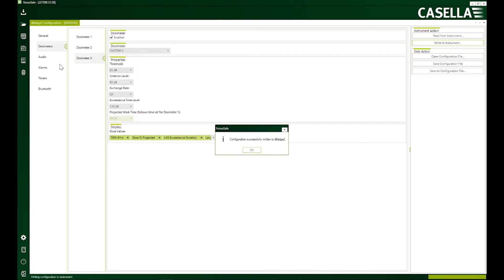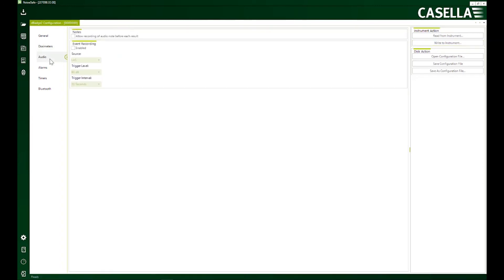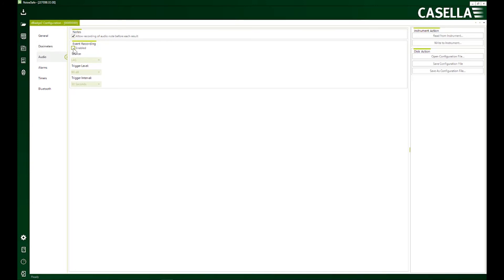And moving down the list, we have got this audio settings here. Notes. This is important. If you select this option, then every time you're going to start a run, the device will ask you to add a voice note so that you remember what was the reading about.